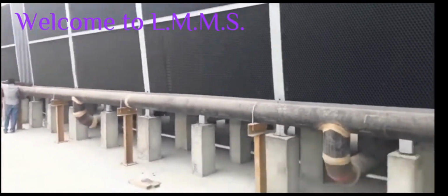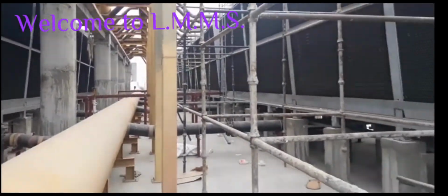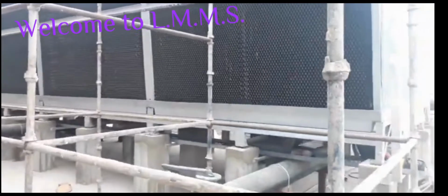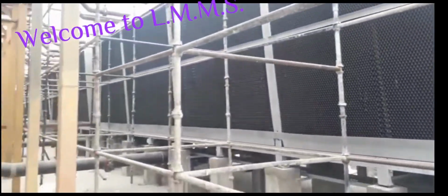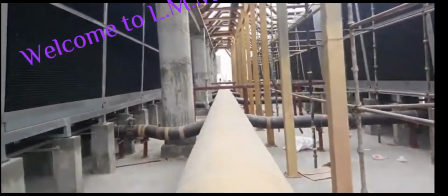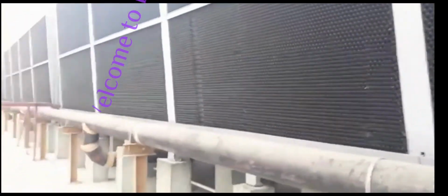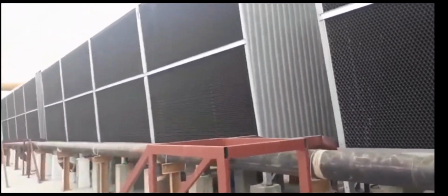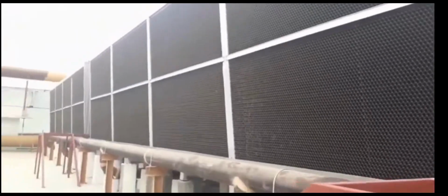TR. As you can see here, these are the inlet and outlet pipes of the cooling towers, and I am going to explain to you the working of the cooling tower in detail. The hot water from the condenser comes to the cooling tower and the water gets cooled and is again sent back to the condenser for cooling of the condenser refrigerant. As you can see here, this is the cooling tower. I am going to explain this plant theoretically as well as practically.